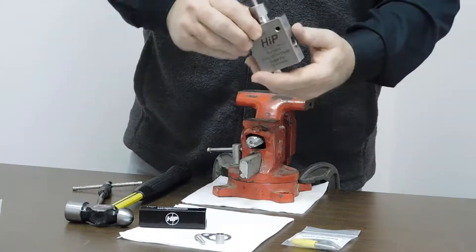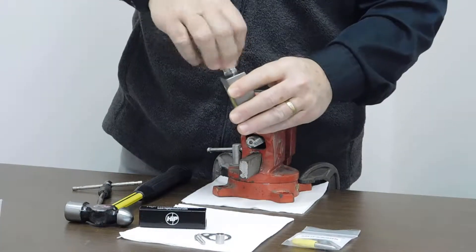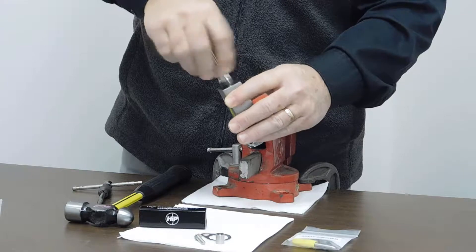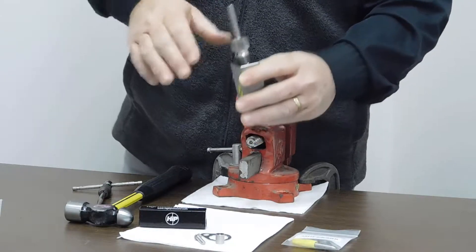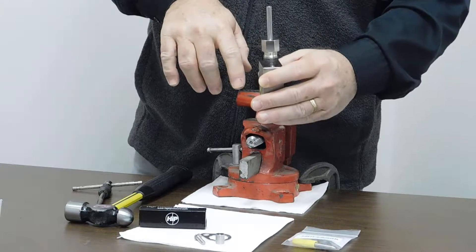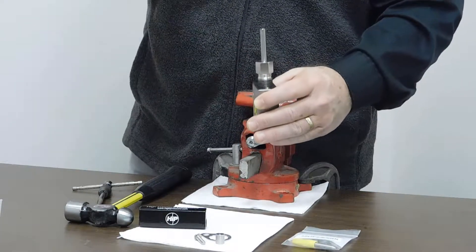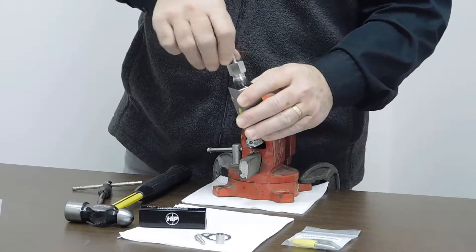The first thing we're going to do today is take the packing gland and stem assembly out of the body. When we do that, we simply rotate it counterclockwise and pull this out. Now there's two scenarios that can happen here. All the washers can stay down inside the block or sometimes, if we're lucky, all the washers and packing come out. Let's see what happens here today.